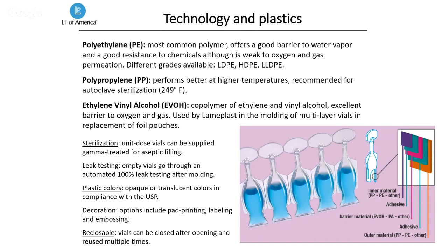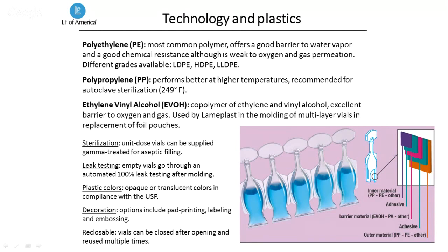We do a gamma irradiation of the vial after molding and prior to transferring those to the filling line. We usually irradiate at 25 kilograys, but of course this can be changed starting from specific requirements and a different protocol for sterilization. The packaging that is then gamma treated is bagged into triple polyethylene bags. We do a 100% fully automated leak testing on each single vial that comes out of the molding line. So there's an automated line that applies a pressure inside the vials and does a leak test.